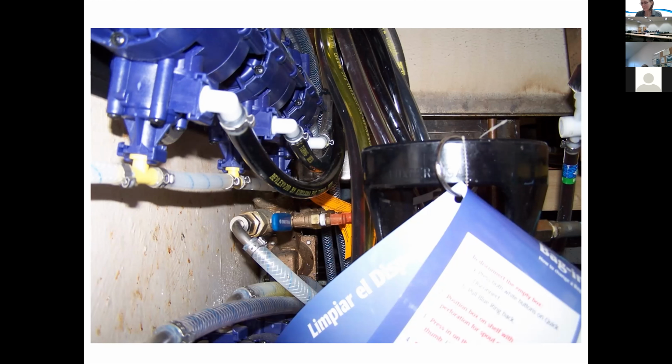I will also say in Washington that WAC 5156 does require an RPBA. A couple of months ago, a Coke distributor on the east side called and was pretty mad at me, because he said everywhere on the West Coast will accept the little plastic dual check with atmospheric vents that come with the soda machine. Every state on the West Coast accepts that, he said. Well, that is not true, and anybody that tells you that is wrong. WAC 5156 does require a reduced pressure principle backflow assembly for soda machines, and that's because of the carbonation.